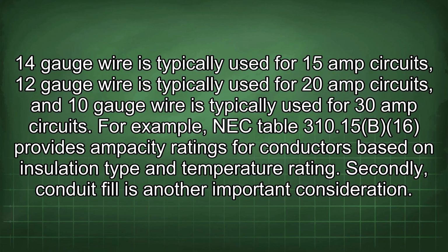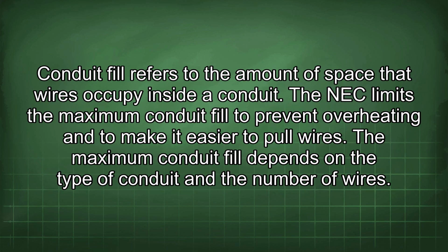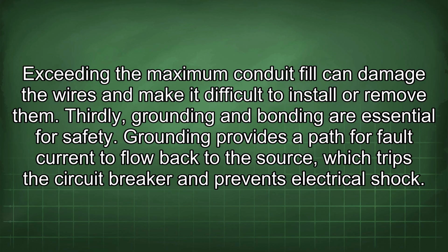Secondly, conduit fill is another important consideration. Conduit fill refers to the amount of space that wires occupy inside a conduit. The NEC limits the maximum conduit fill to prevent overheating and to make it easier to pull wires. The maximum conduit fill depends on the type of conduit and the number of wires. Exceeding the maximum conduit fill can damage the wires and make it difficult to install or remove them.